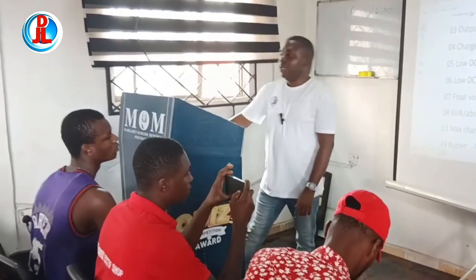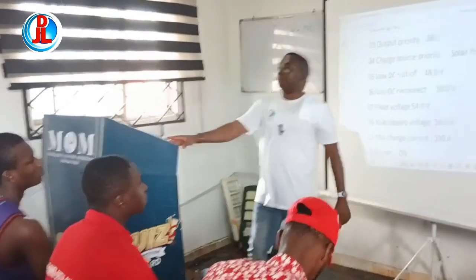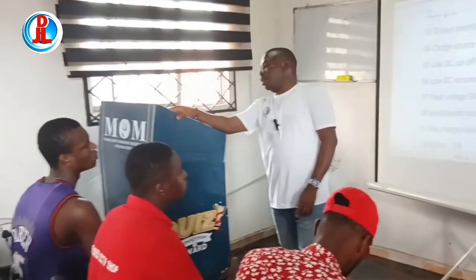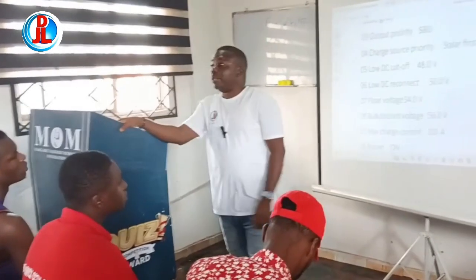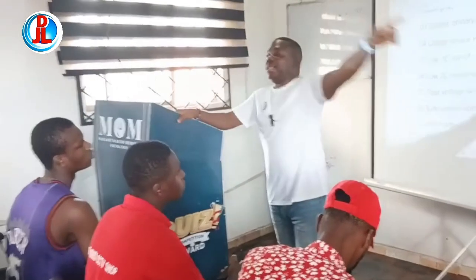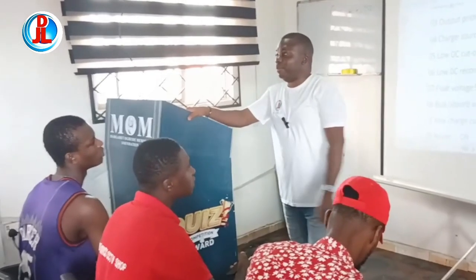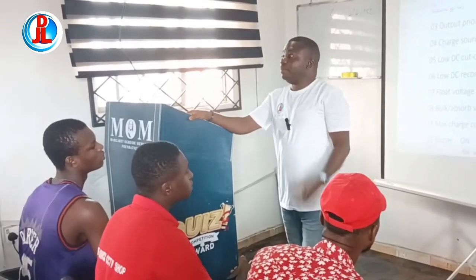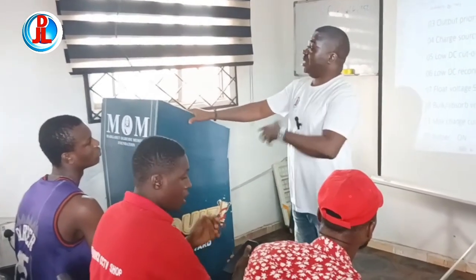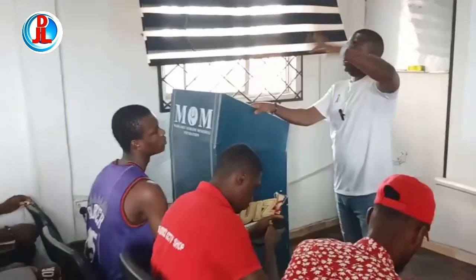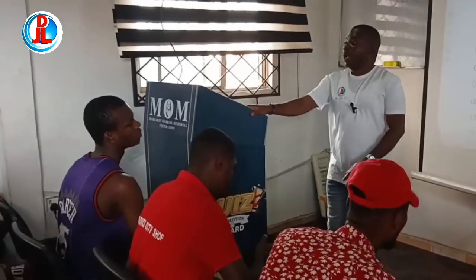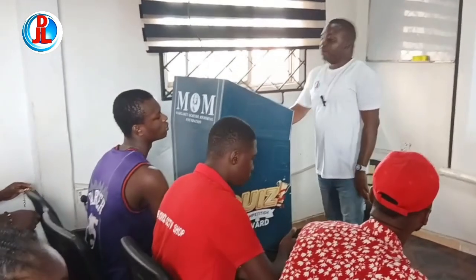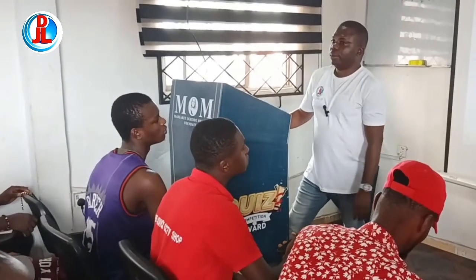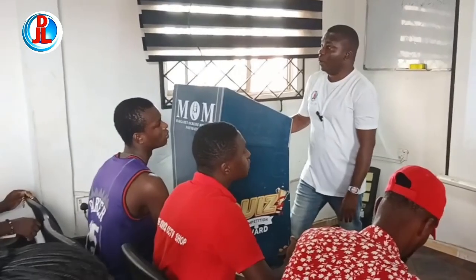Are we together? The reason why some of the batteries will remain on 90% is because there is no bulk voltage set. Some of them, go back and check, the bulk voltage is 54. Because of that, it will not enter 100%. It's not as if it's not charged. It flows into that 100% when it's operating on that bulk voltage. The maximum charge current, 100. Hello? Set it.